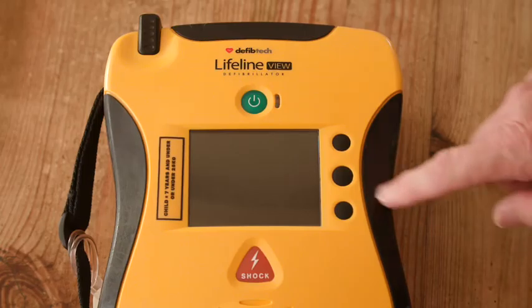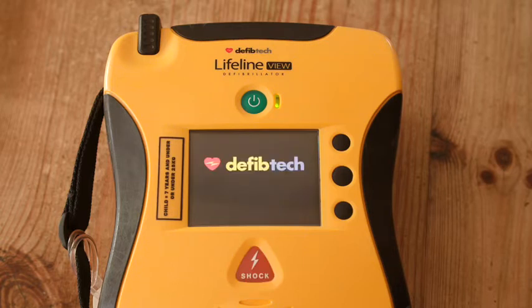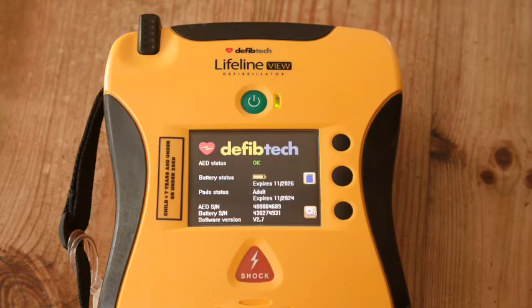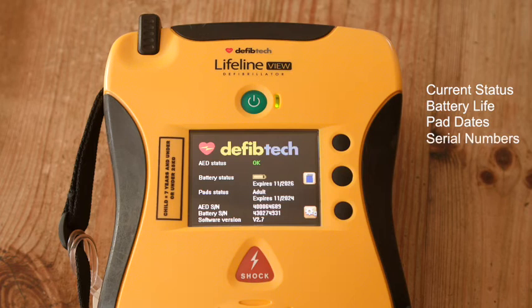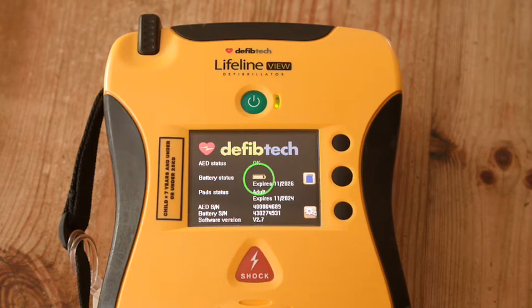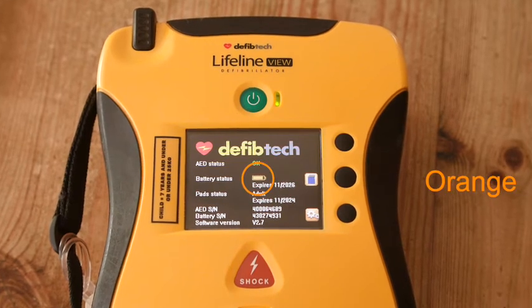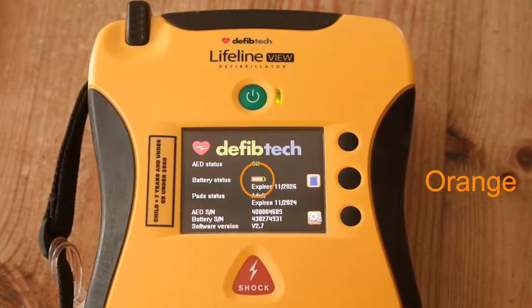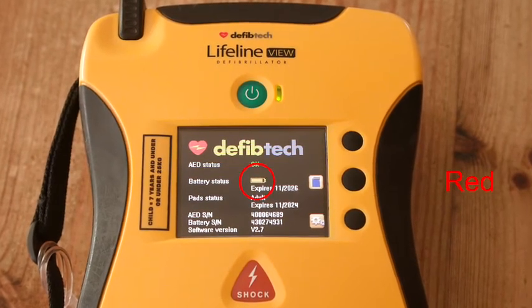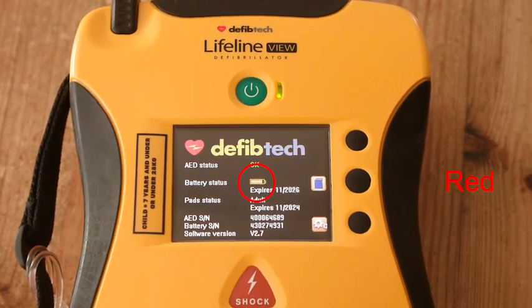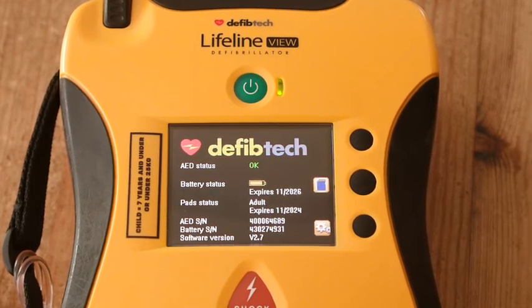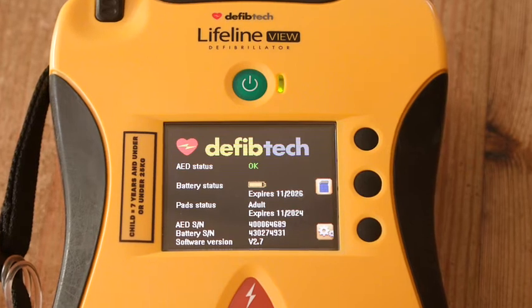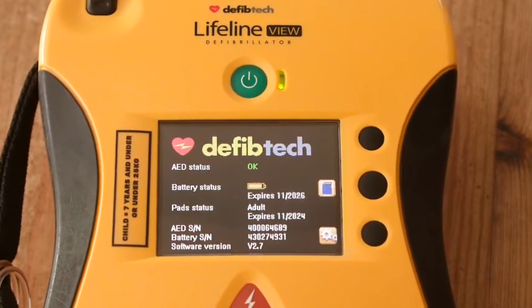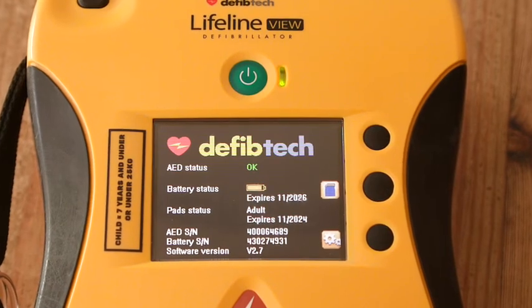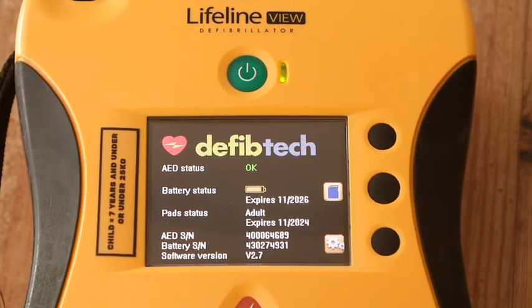Once a month, or if there is an error, press the middle black button to run a short self-check. The defibrillator will display a table showing the current status of the defibrillator, the battery life, the pad's dates, and any software serial numbers. The battery fuel gauge shows green when new, then orange, then when the battery is almost flat, and only has a few weeks left, it will change to red. The batteries last about 4 years if the defibrillator has not been used, so if this is orange, this is actually okay. If the indicator is red, then time to order a new battery. You can use the information shown to give us any details on the reports. This screen will disappear on its own.